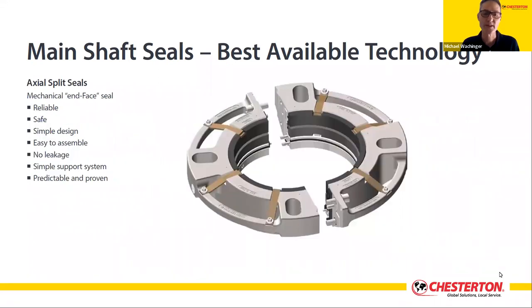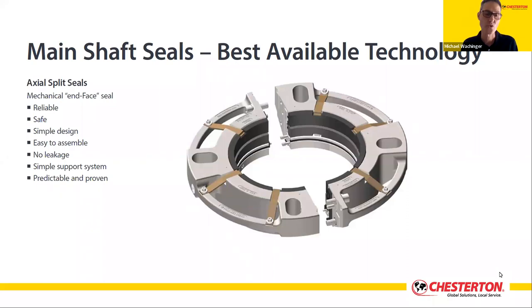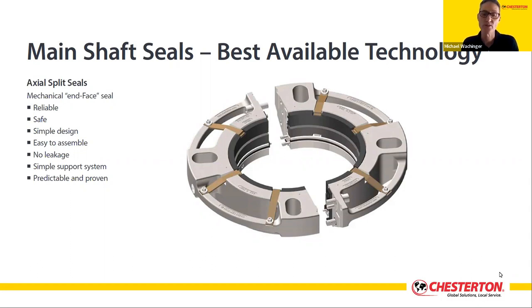With increased uptake of new technology, not only by end users but also by hydroturbine OEMs such as Andritz in Europe for installations all around the world, the growth of this technology continues. The benefits of ease of installation, minimal leakage, minimal and in many instances no clean-as-possible flush water requirement, together with predictable life due to worldwide experience and visual or electrical wear indications, make this latest technology a viable option for both retrofitting to older equipment and for new designs and installations.